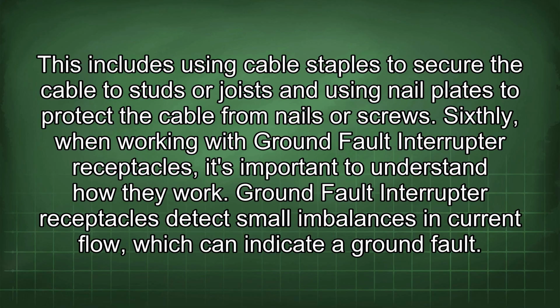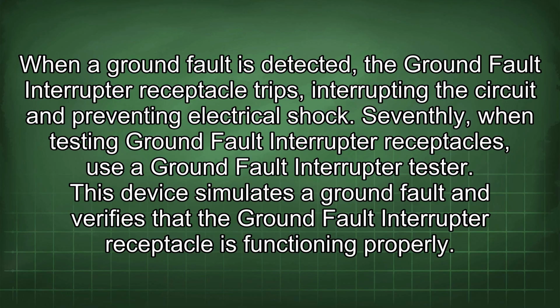Sixthly, when working with ground fault interrupter receptacles, it's important to understand how they work. Ground fault interrupter receptacles detect small imbalances in current flow, which can indicate a ground fault. When a ground fault is detected, the ground fault interrupter receptacle trips, interrupting the circuit and preventing electrical shock. Seventhly, when testing ground fault interrupter receptacles, use a ground fault interrupter tester. This device simulates a ground fault and verifies that the ground fault interrupter receptacle is functioning properly.